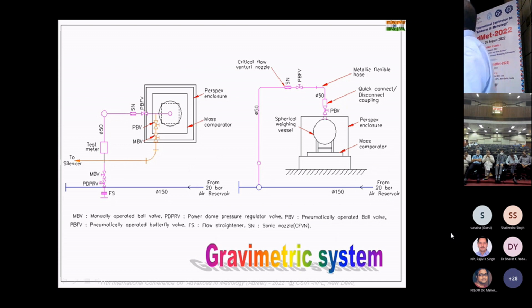But basically, if you take the mass measurement with the piping connected, it will not be correct because the tension on the piping will influence the mass measurement. So to get the correct mass, the entire vessel has to be disconnected from the piping. Here we have a three-part coupling. At the start of the run, we disconnect it and tare the balance. After connecting, we continue the process. At the end, the entire piping is under pressure, so we cannot detach it directly. So a small portion of air from this area we have to discharge, then decouple it from the other piping, and again take the mass measurement.